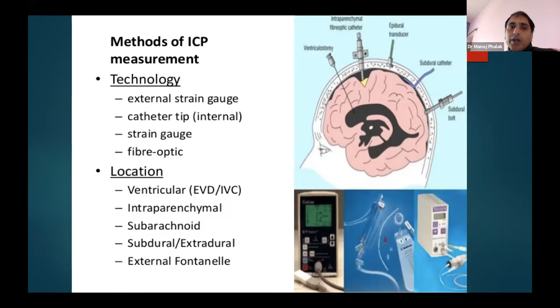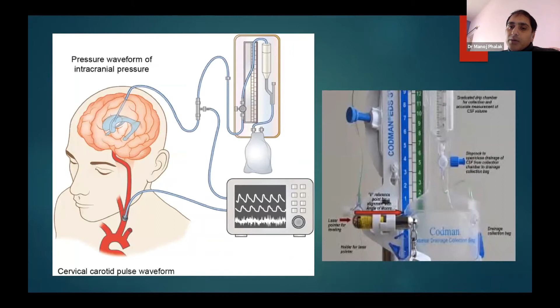The technology is based on simple piezoelectric effects, or it can be based on strain gauge, just like CVP measurements. So in this case also, just like CVP measurement, it is very, very important to check the waveform of the ICP measurement, because sometimes the waveform may be dampened and the catheter may be misplaced. If we are using a strain gauge method and the catheter is not in the ventricular system, it has migrated to the parenchyma, then it may not show the correct pressure, and vice versa.